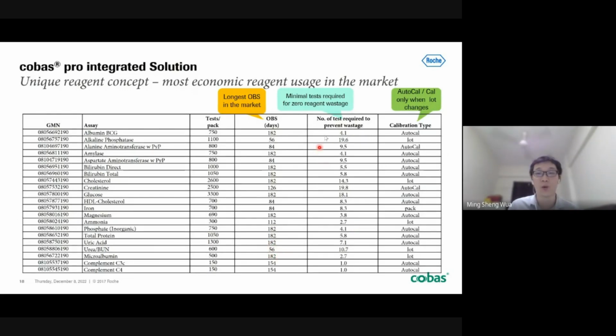This in a way also helps you to prevent wastage. If you look at this column over here, it shows you how many tests per day you need to run on average so that you don't have any wastage. For example, for albumin, if you have more than 5 tests per day, then you will not have any wastage at all. So the number of tests required for no wastage is really minimal when it comes to Roche. And as I mentioned earlier, when it comes to calibration, for most of the substrate and enzyme assays we are able to do auto calibration, while the rest is mainly by-lot calibration.